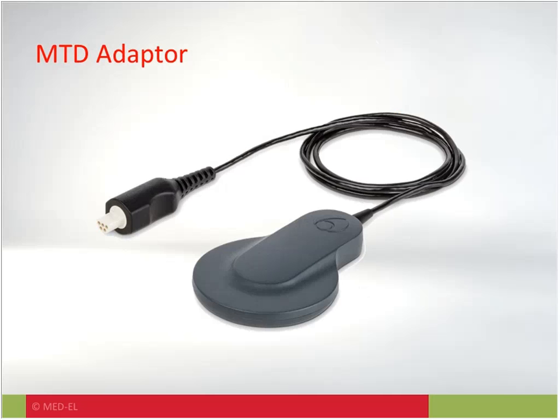So I'm going to start by giving you a little bit of history about why we released an adapter for our microphone test device. MED-EL has a microphone test device already for the Opus 2, which some of you therapists might have seen. The Opus 2 is the behind-the-ear speech processor that was out prior to the SONNET. So this MTD was not compatible with the SONNET. We couldn't use it with our SONNET device. And so we released this MTD adapter so that the Opus 2 microphone test device could be used to listen to the microphone on the SONNET. So it's really just a way of bridging the two.